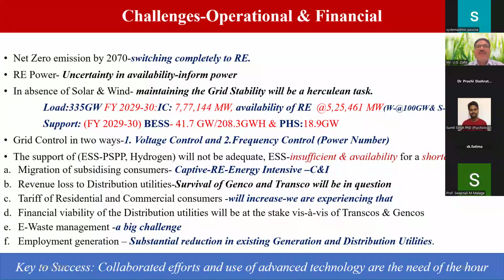Then when we say how the grid is operated nationally, okay, there are two kinds of methods. One is the voltage control method, and the second one is frequency control. More often, frequency control is preferred. That is, let us say our power demand is 250,000 megawatt, and power supply is also around 250,000 megawatt. So the power number, this is a very interesting number, will decide the level of the frequency. The power number 250,000 by 50 frequency comes to 5,000 when installed capacity and power demand is 250,000.